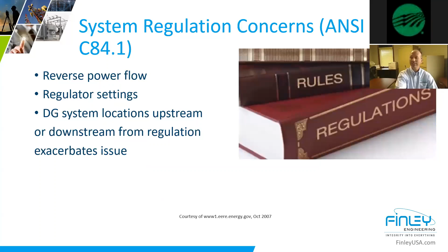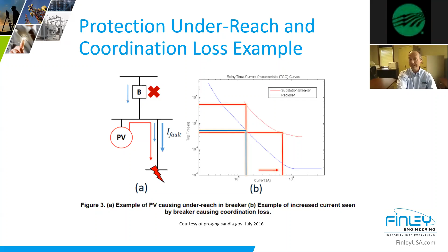Okay. All right, I'll come back to that point because we will talk about that just a little bit more here in a few minutes. Okay, so kind of back to this point then, the coordination example. Like I said, that's a good one that kind of demonstrates the potential that you may have a breaker not doing its job because, if you think about it intuitively, you've got a local fault feeding source that is going to react very quickly to a fault. And we'll talk about that again in a minute. But it could do it before your breaker device that maybe doesn't have a fast enough trip potential.